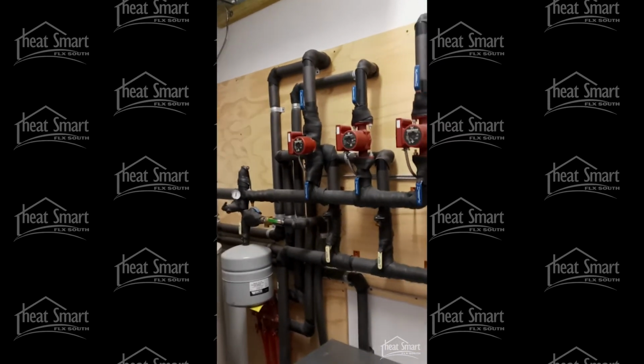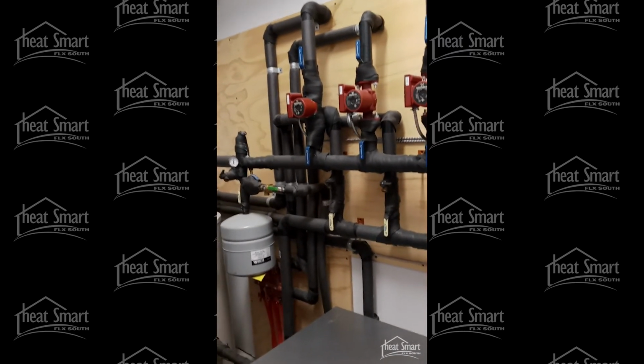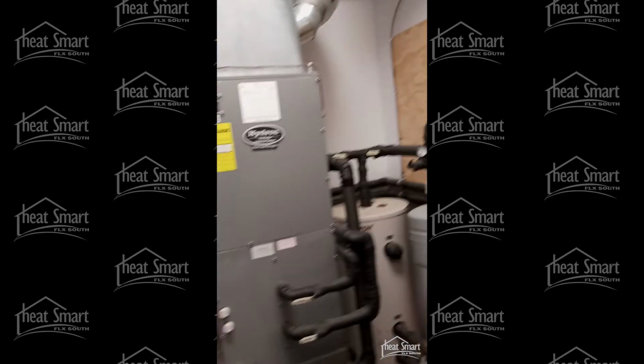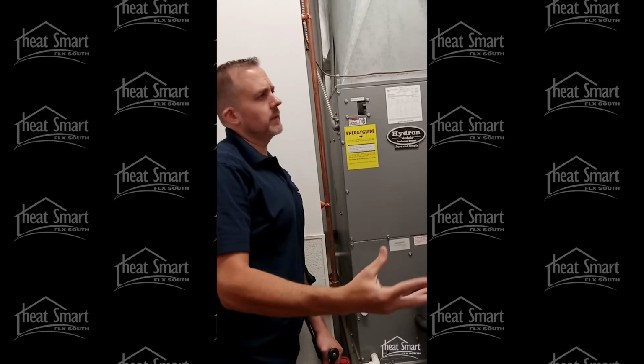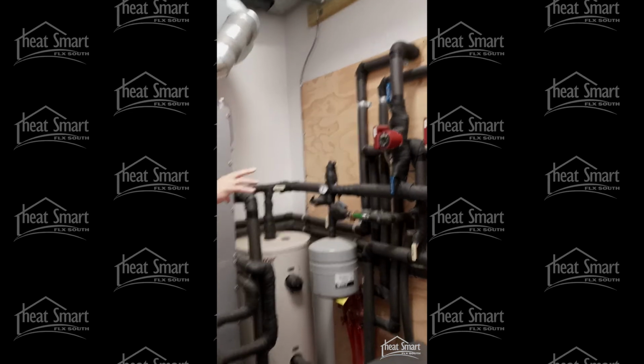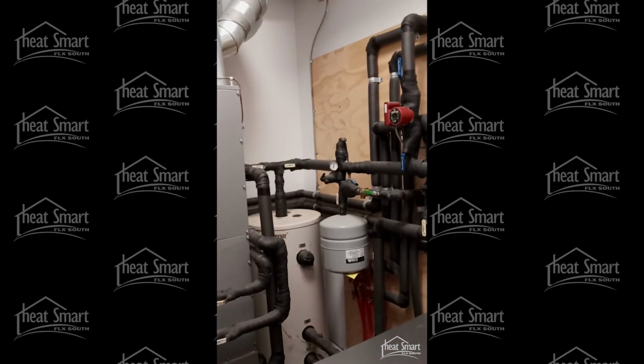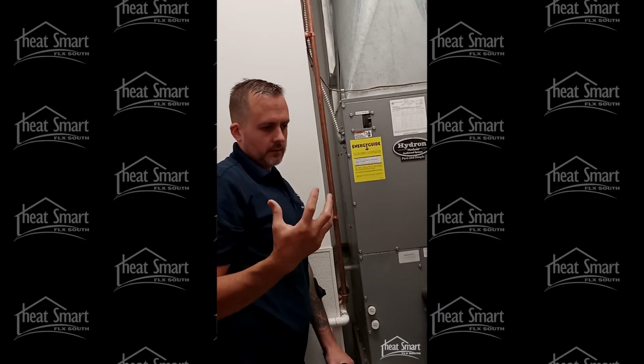And the reason you see all this is insulated. Yeah, that looks pretty thick. It's indoors, so why do we need it in a conditioned space? From a heating perspective, it helps keep the heat in the lines, to keep the water hot and everything efficient, so you're not wasting heat. But for cooling, it's really important because now cold water is running through some of these pipes during air conditioning, and it's always going to be colder than the temperature in the room.